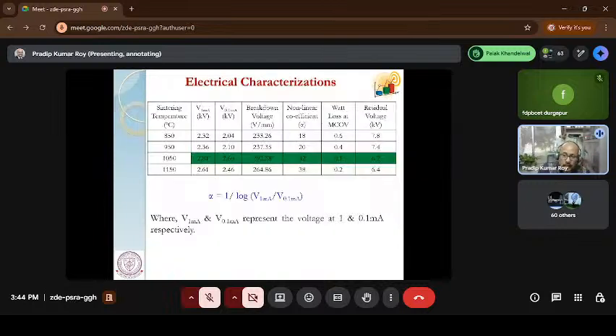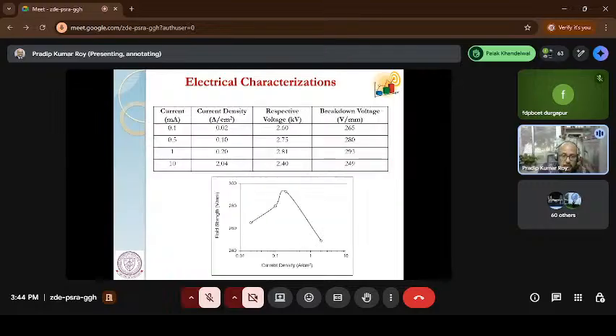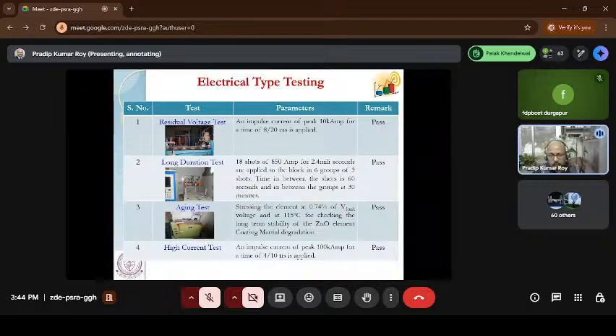Now, I said earlier the breakdown voltage was 120 to 140 volt per mm. Now we achieved around 300 volt per mm. So almost double, just by reducing the grain size from 12 micron to 6 micron. Then we did impulse testing, called residual voltage testing, and high current testing. Residual voltage testing tells how much initial strength the body can withstand, with an 8 by 20 microsecond impulse. We are applying around 10 kiloampere current.